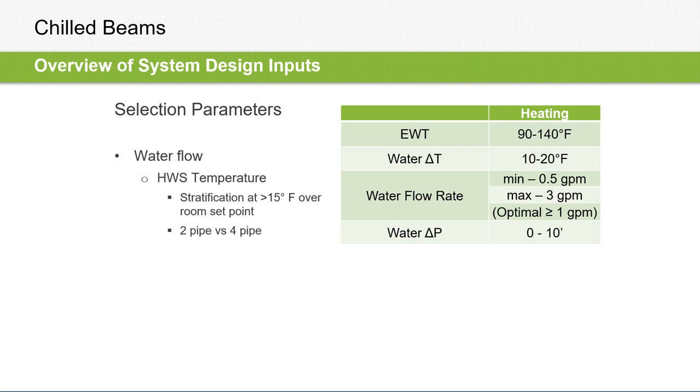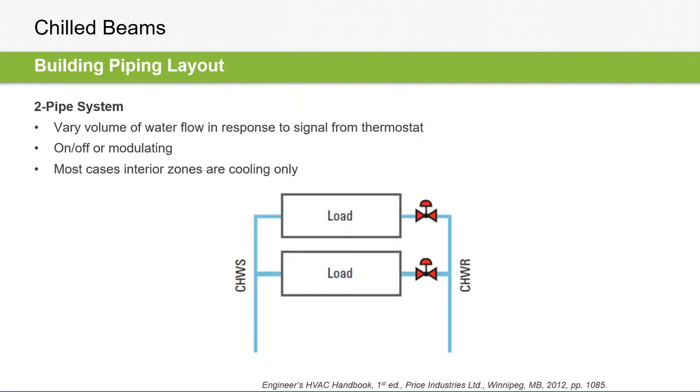And so the chilled beams are going to have, with the 4-pipe system, we'll circuit the pipe a little bit differently. So you have the same fin block, the same coil passing, and all we do is we dedicate a couple passes over to heating. So nothing changes in the water coil. It's not two separate coils in there. It's just the same fin block. We just give away a couple passes for heating. So that's how the 4-pipe works. Then again, you have two isolated loops, so you can control them both individually.